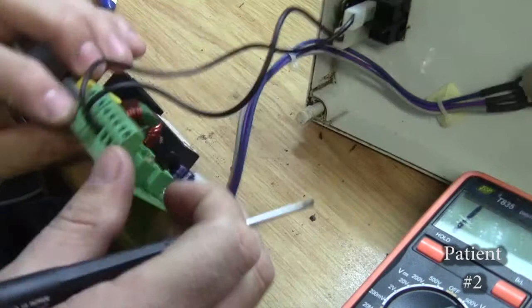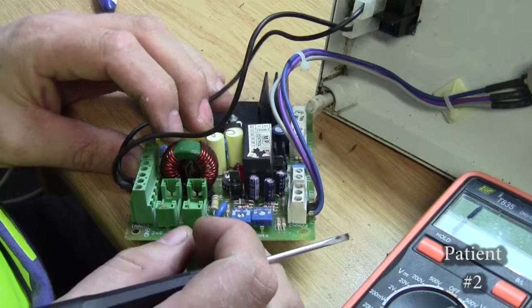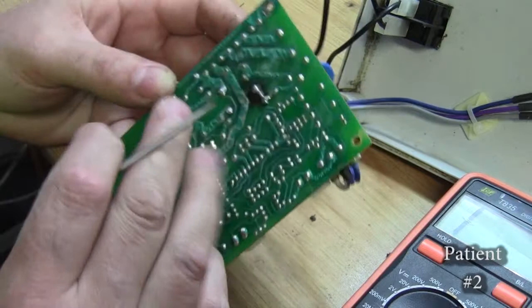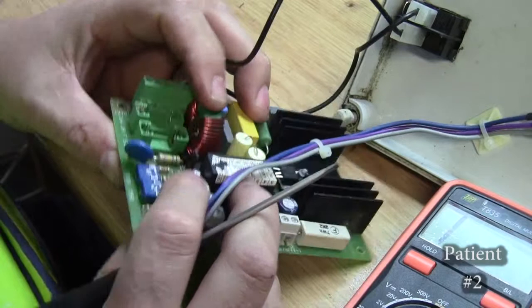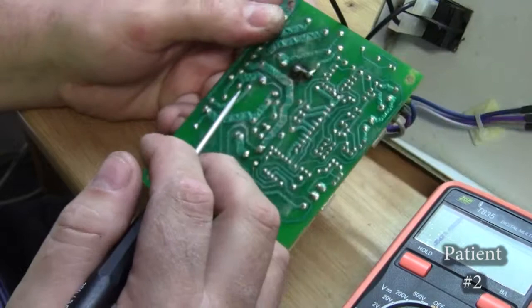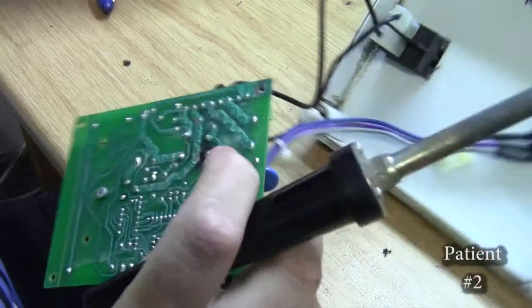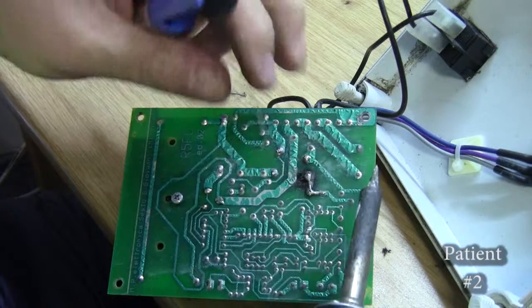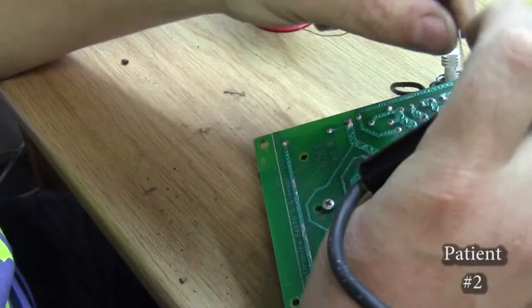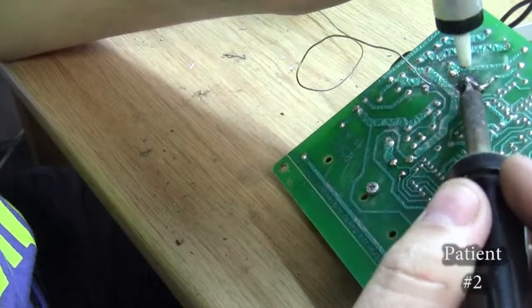The pin is right through the board and the fuse holder pin. That's the fuse holder pin on there. You can see there is actually melted plastic in the fuse holder. I don't know if you can see that there. So I think I need to pull out that fuse holder. And throw my screwdriver on the floor. That's always important to do. Throw your screwdrivers on the floor. Oh no, we don't need no screwdrivers. Yeah, the fuse holder is toasted. I wonder if that could have just been a poor contact on the part of the fuse.